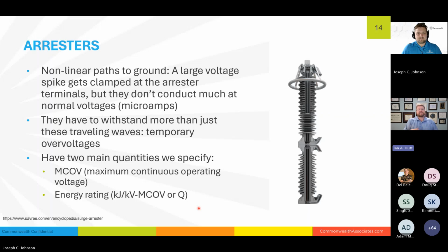Talking about the different types of applications, for this presentation we're really focused on lightning and switching events. However, there are other events that happen on the system, called temporary overvoltages. This is when you may have a fault that's driving voltages to higher levels. We won't cover it too much here, but just as a note, these arresters will activate and operate for all voltage levels that are within their operate range. So if we have a fault that drives the unfaulted phases to higher voltages, based on grounding conditions and grounding types of a system, these arresters may operate as well. And it is a consideration when you're thinking about sizing this equipment.